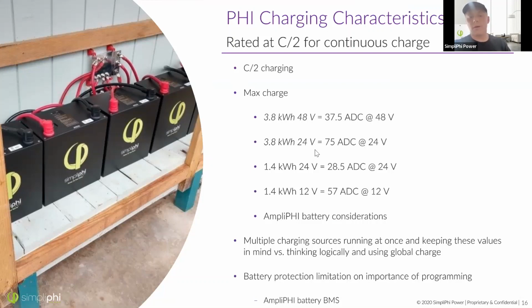Our 24 volt battery is 151 amp hours. You're going to divide that by 2, you get about 75 amps DC. So on and so forth. All of our products have the same charge and discharge rate, so it's very easy to figure out. For example, our new battery is about 5 kilowatt hours. You're going to divide that by 2. The discharge rate is 2.5 kilowatts.